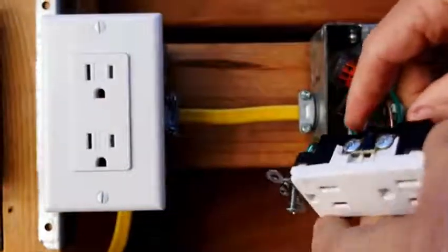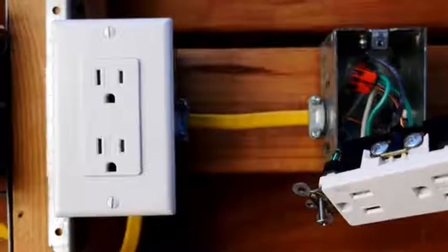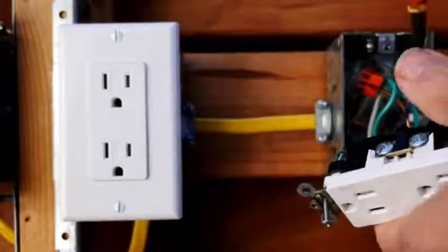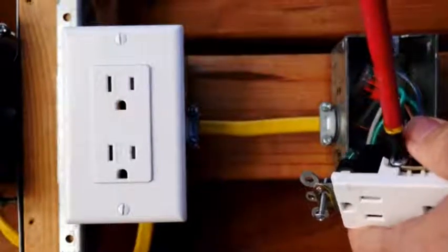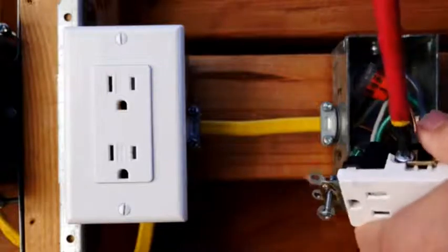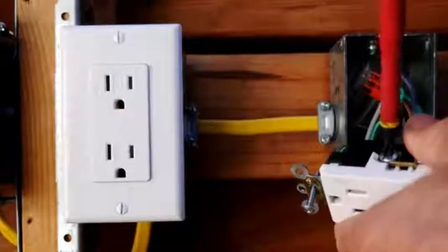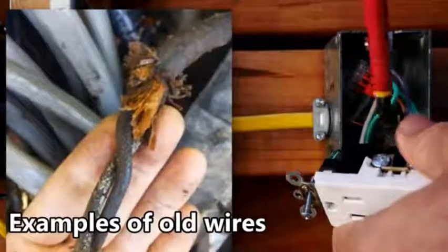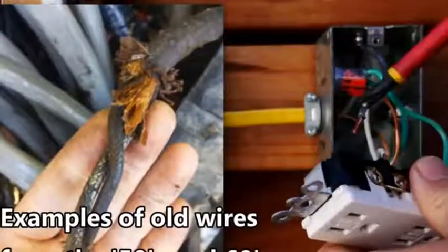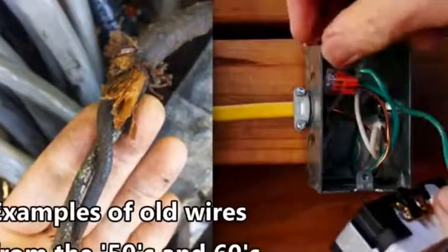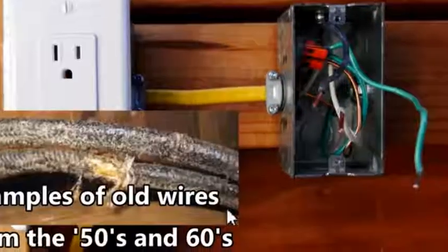So this is incorrect. One of the big reasons for reverse polarity receptacles is that over the years in the older houses, the hot wire and the neutral wire both turn gray, and they're really the same color. This is what I'm talking about, houses from the 50s and 60s and so forth. And it's really difficult to tell just by looking at them.